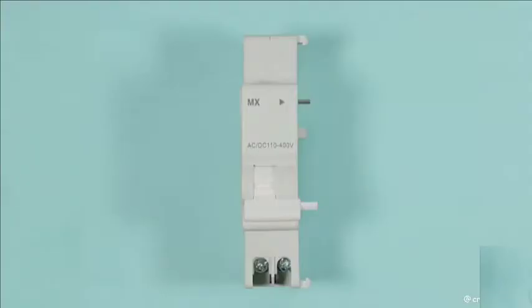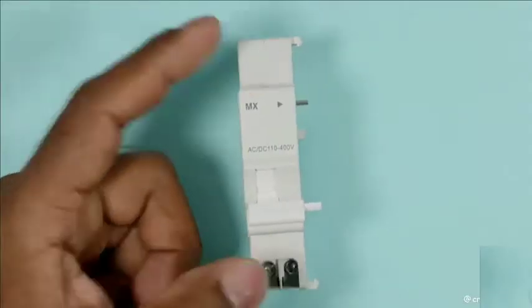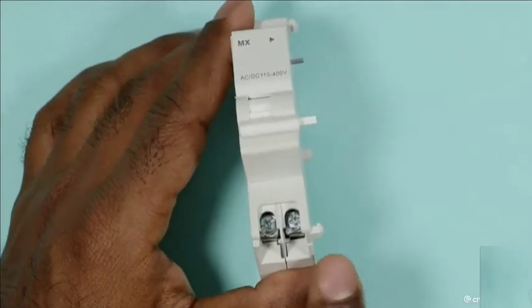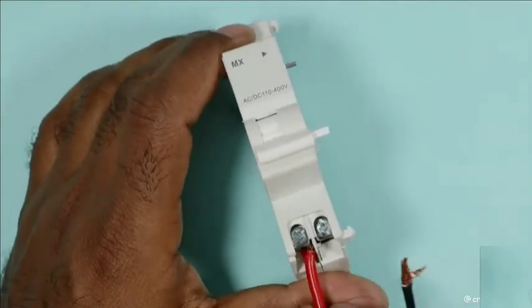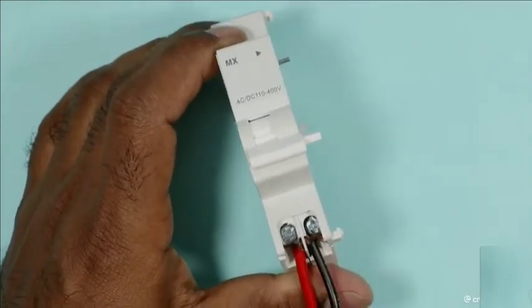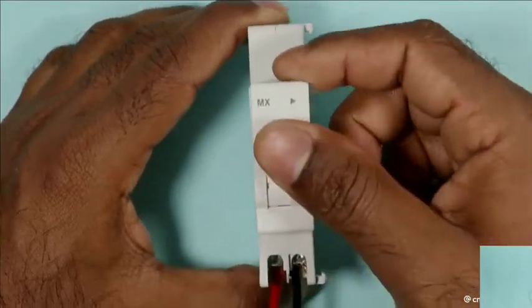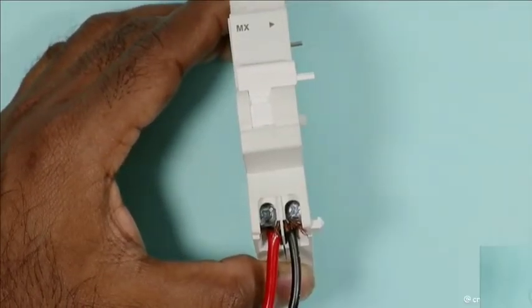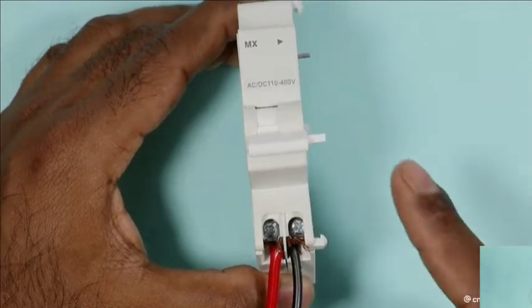In the same way this shunt release coil works. In this coil you will find two terminals, and if you connect phase supply and neutral supply to these terminals and after this if you switch on this coil and switch on the power supply of wires, then this shunt release coil will trip.